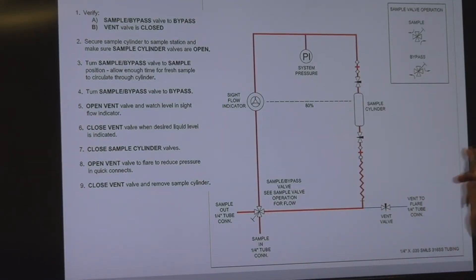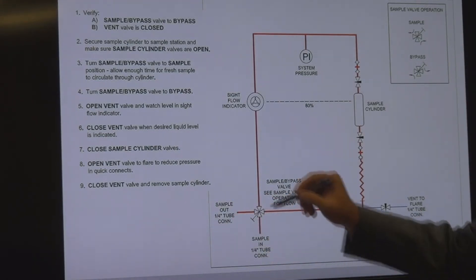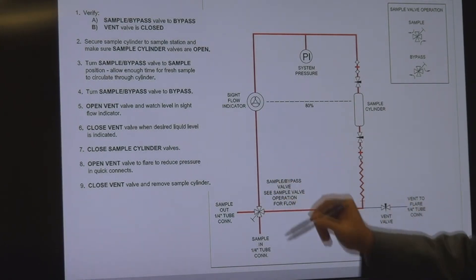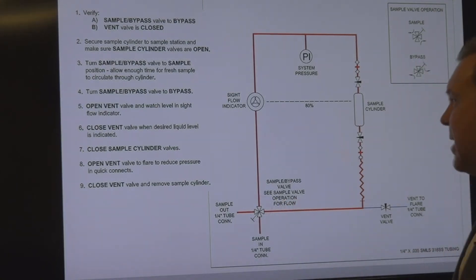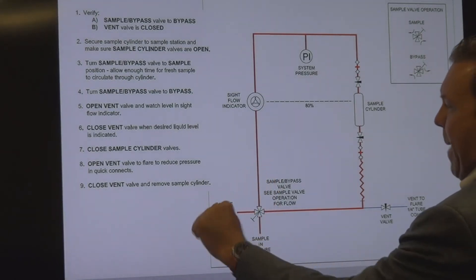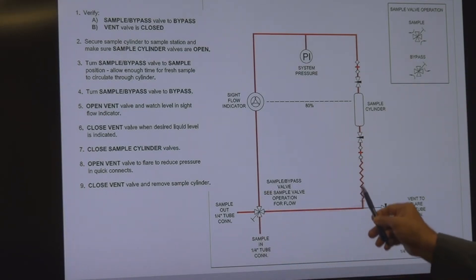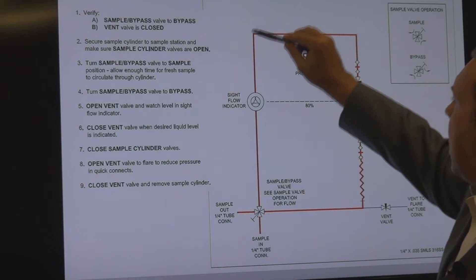This flow diagram demonstrates the flow loop on the sample panel. Under normal conditions, we're flowing in through the in port and out through the sample valve — this is a four-way sample valve. In bypass position, these two ports are common and those two ports are common, so we're continuously flowing through the sample panel to always have a representative sample. When you turn that single handle from bypass to sample, the port commonality shifts and we're now flowing up through the system and through the cylinder. We'll pick up system pressure on the PI and see flow through the sight flow indicator, then back out — continuously circulating through the system.